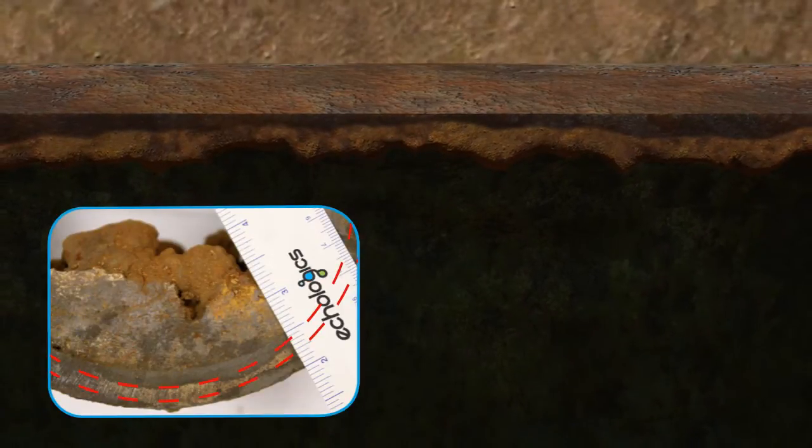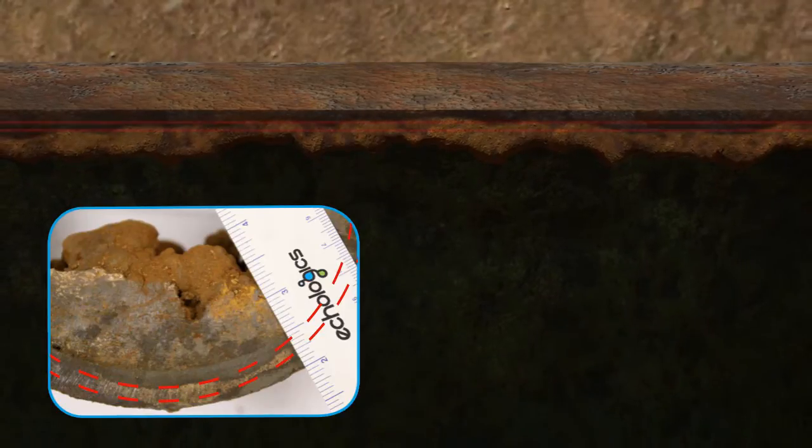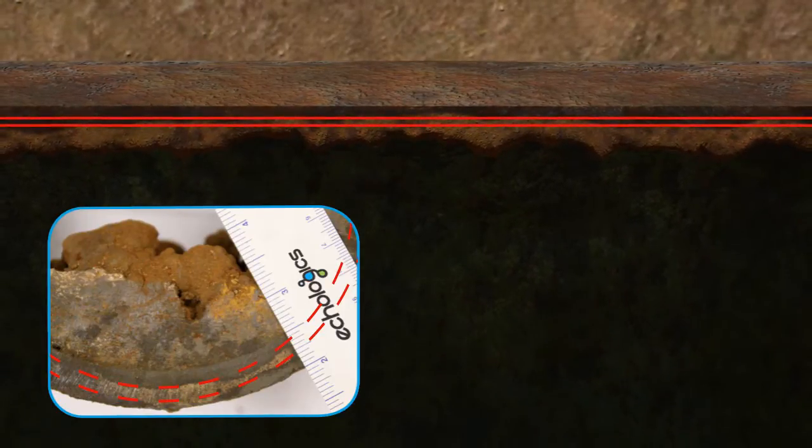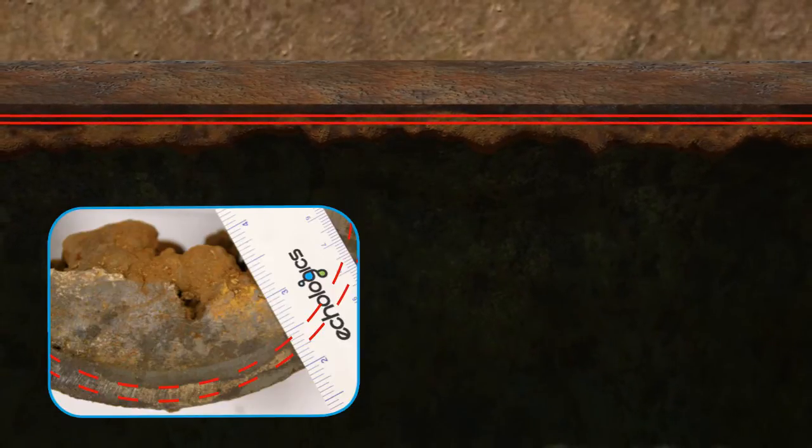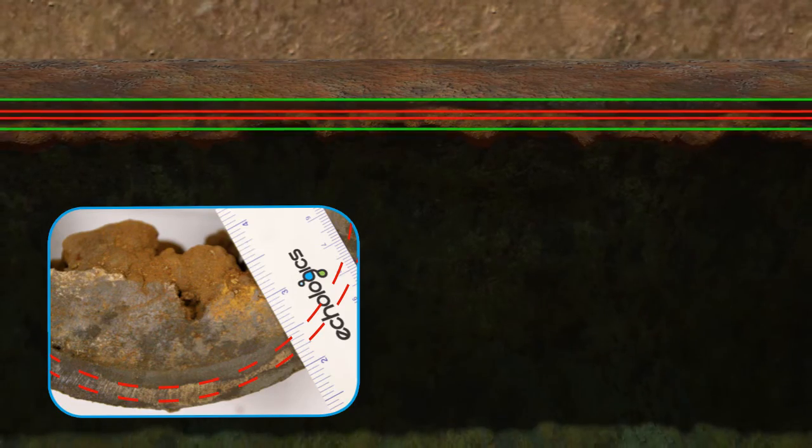Echologics' field engineers use advanced algorithms to convert the data into a measure of the average minimum wall thickness of the inspected pipe segment. The calculated wall thickness measurement is compared to the original thickness of the pipe to determine the average percentage of wall loss.